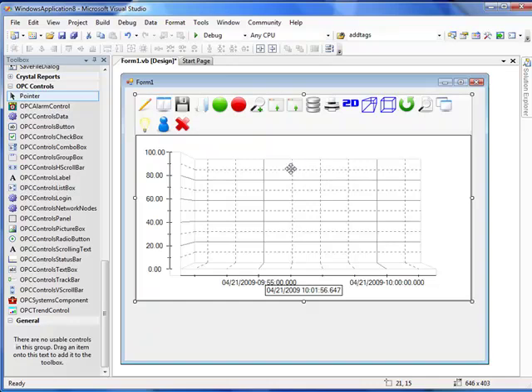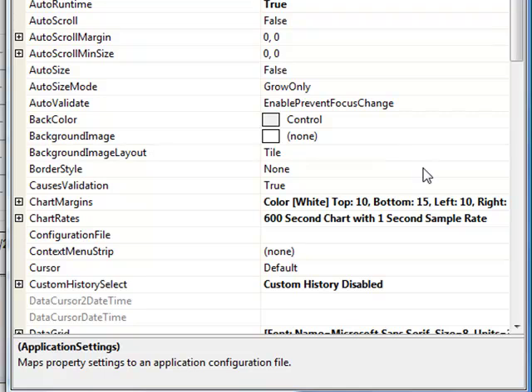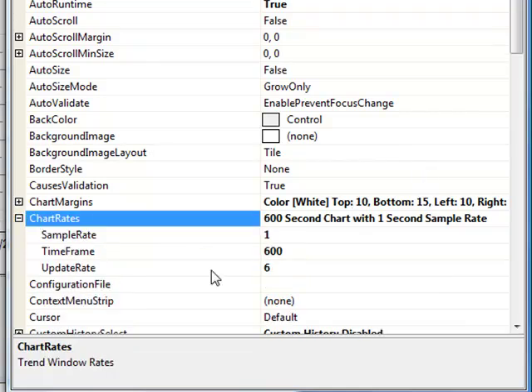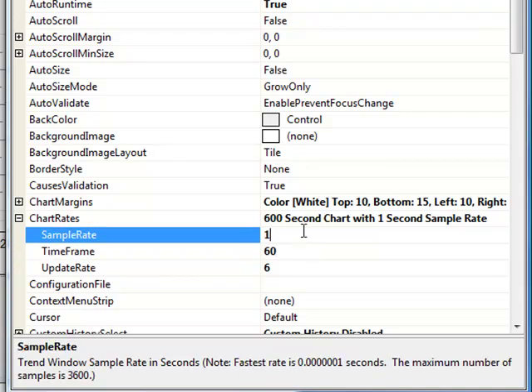We're now ready to set properties for the trend control. Let's start with the chart update rate. If we go down to chart rates, we can set the time frame to any value in seconds that we would like. We're going to use one minute in our time frame scale. A sample rate can be anything you would like — you can use sub-second trending as well.